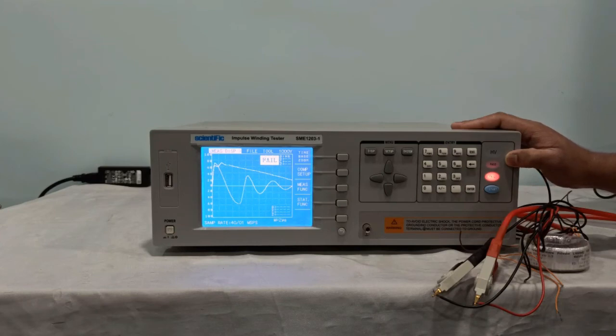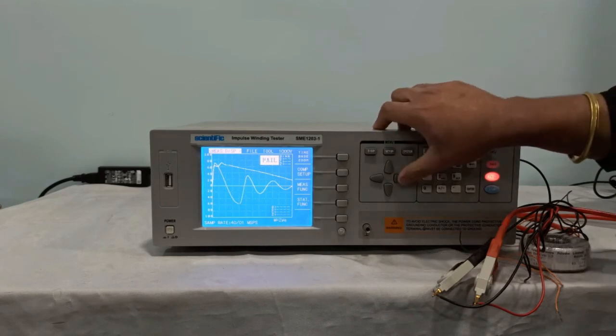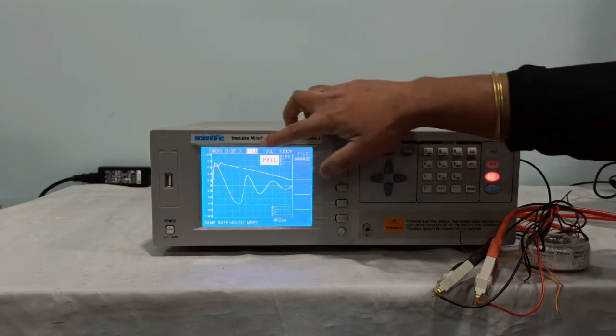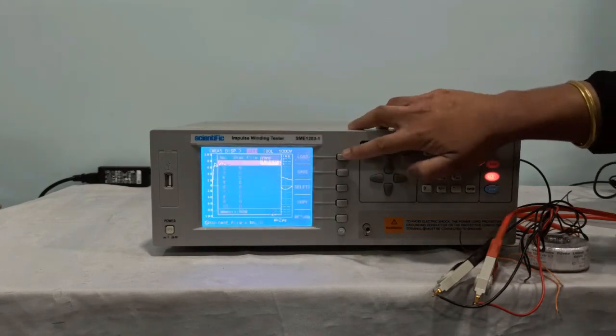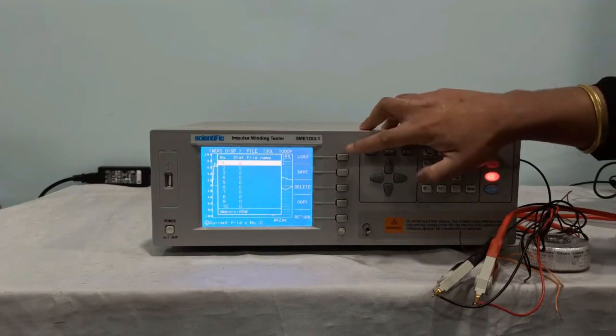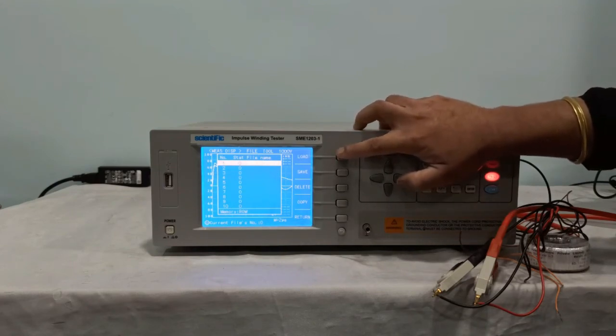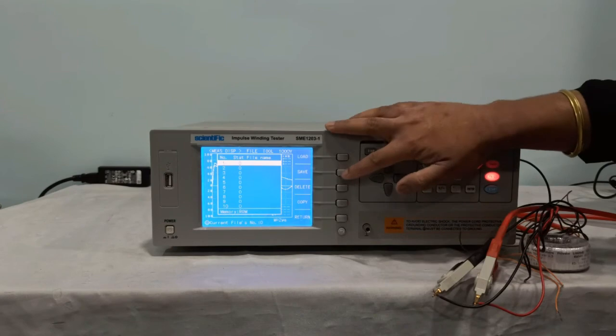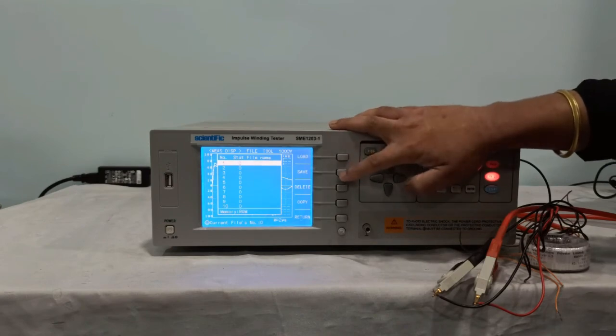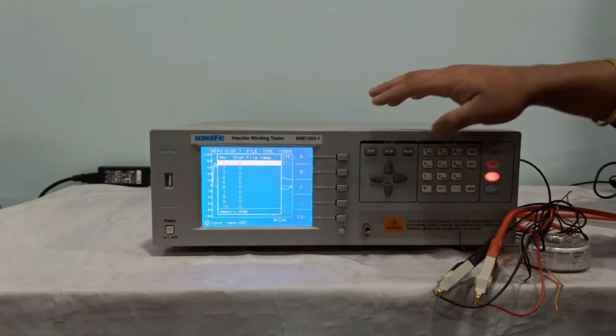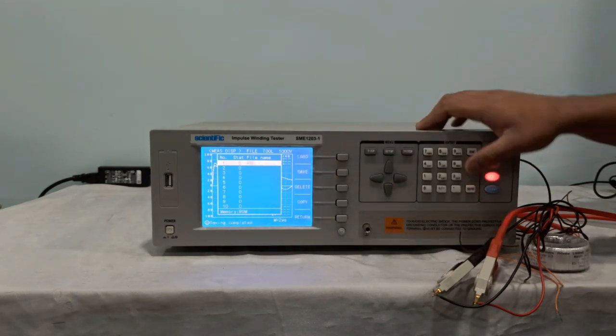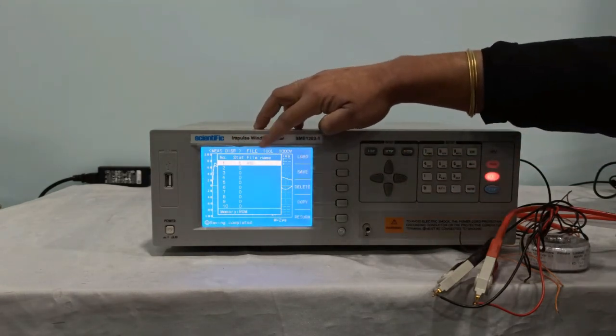You can also store this standard waveform in the memory of this instrument. What you have to do is go to file. Once you are in file, go to file manager. In file manager you have options like load, save, delete. So you have to save. In order to save the standard waveform, just press save, input the file name, suppose ABC, and press enter. So in the first location the ABC file is stored.